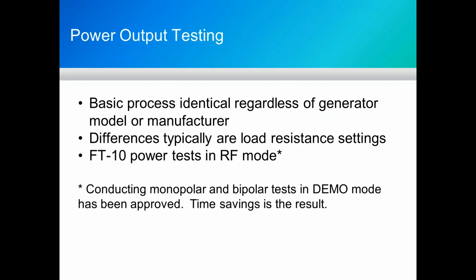So as I mentioned earlier, the basic process here is going to be identical, regardless what generator model or manufacturer we're looking at. For instance, the connections will be the same between a Valleylab generator and an Erbe generator, except Valleylab for cut likes 300 ohms. Erbe will have you do that test at 500 ohm load resistance.